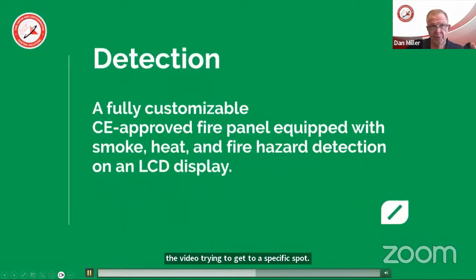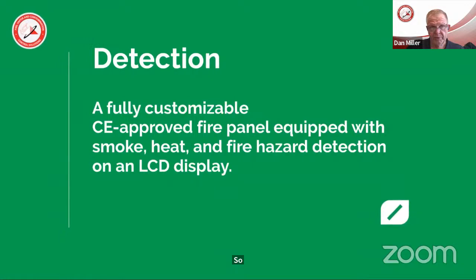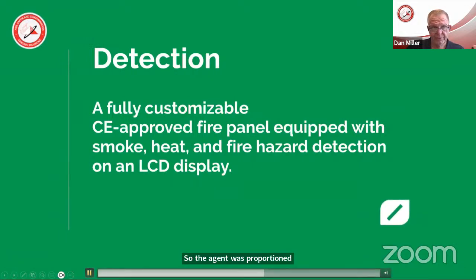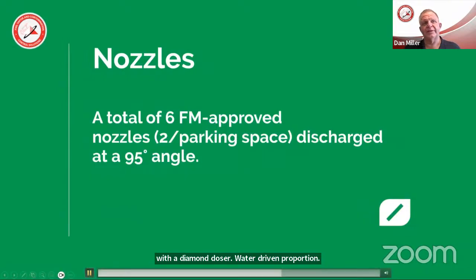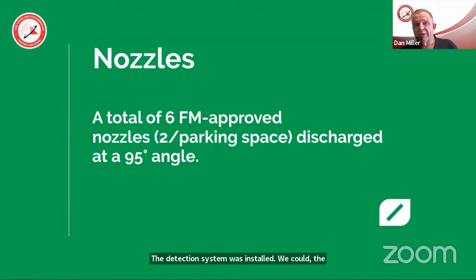The agent was proportioned into the sprinkler risers with a diamond doser, a water-driven proportioner. The detection system was installed. Detection is kind of its own animal when it comes to lithium-ion batteries—one of the big problems is that they can produce a lot of gas before they ever produce fire, and can actually become explosive. So you have to think about that factor as well.